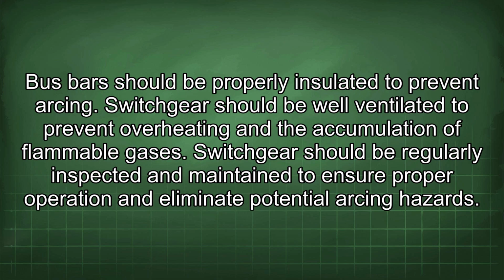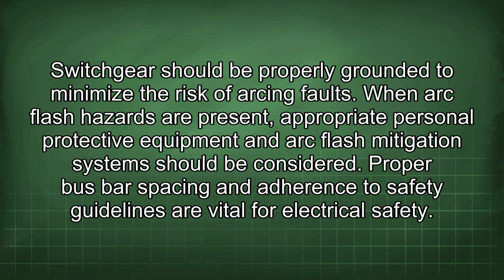Bus bars should be properly insulated to prevent arcing. Switchgear should be well ventilated to prevent overheating and the accumulation of flammable gases. Switchgear should be regularly inspected and maintained to ensure proper operation and eliminate potential arcing hazards. Switchgear should be properly grounded to minimize the risk of arcing faults. When arc flash hazards are present, appropriate personal protective equipment and arc flash mitigation systems should be considered. Proper bus bar spacing and adherence to safety guidelines are vital for electrical safety.